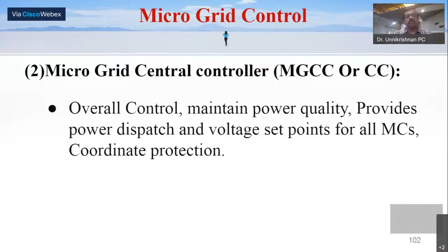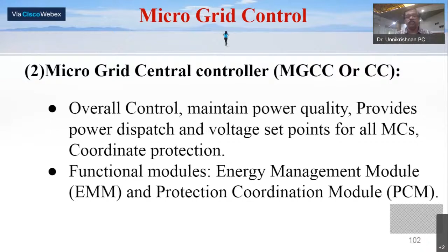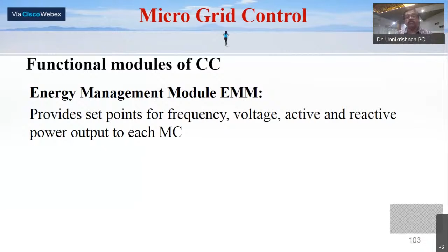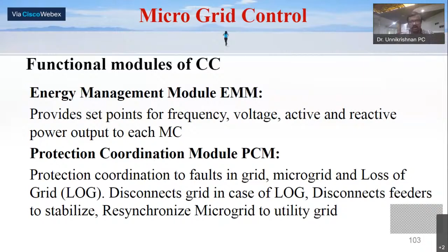The central controller looks after the overall control and maintains the power quality. There are two modules within the central controller. One is the energy management module, EMM, and the second is the protection coordination module. The energy management module provides voltage and frequency set points to the micro source controllers. Also, it provides the active and reactive power requirement for each micro source controller. So the micro source controller should see that the frequency and the voltages are maintained as decided by the energy management module. Secondly, the protection control coordination module looks after the faults in the grid, loss of grid, disconnecting the grid, resynchronizing the grid with the utility, etc.